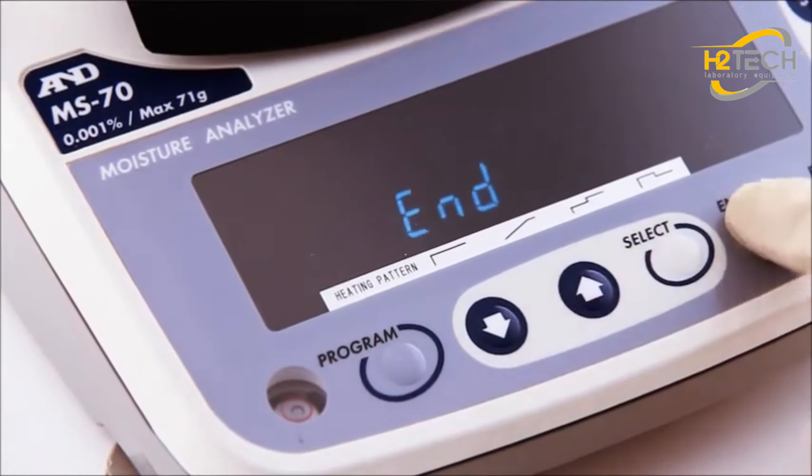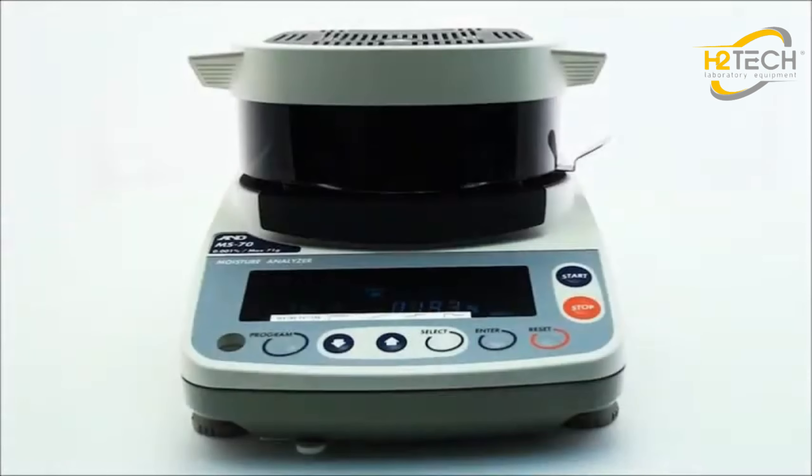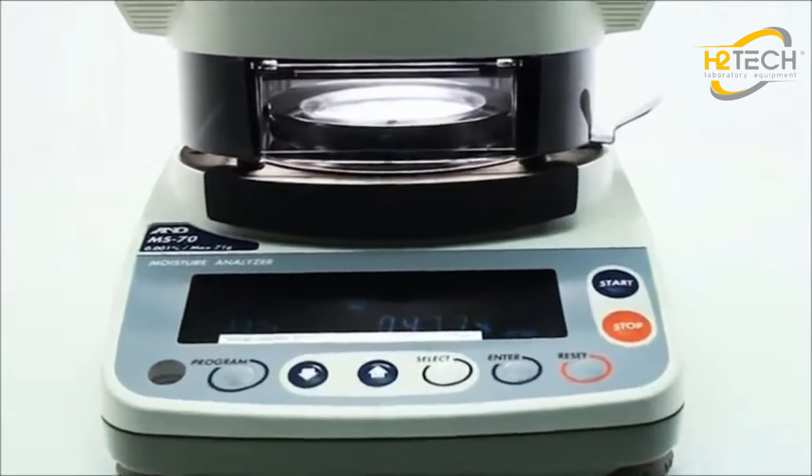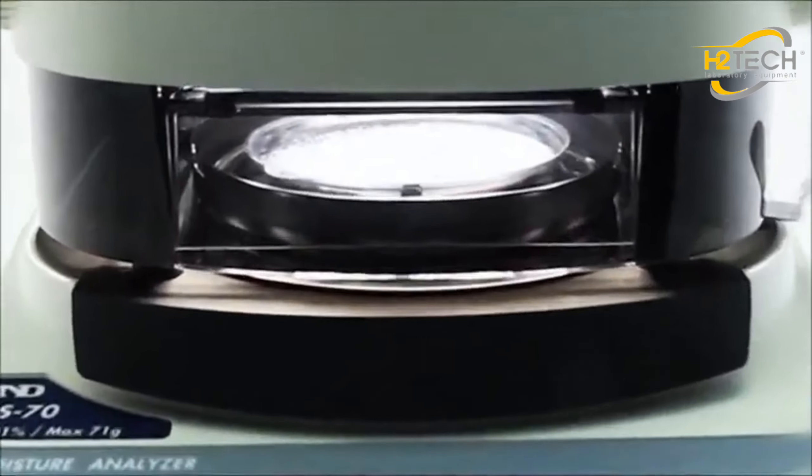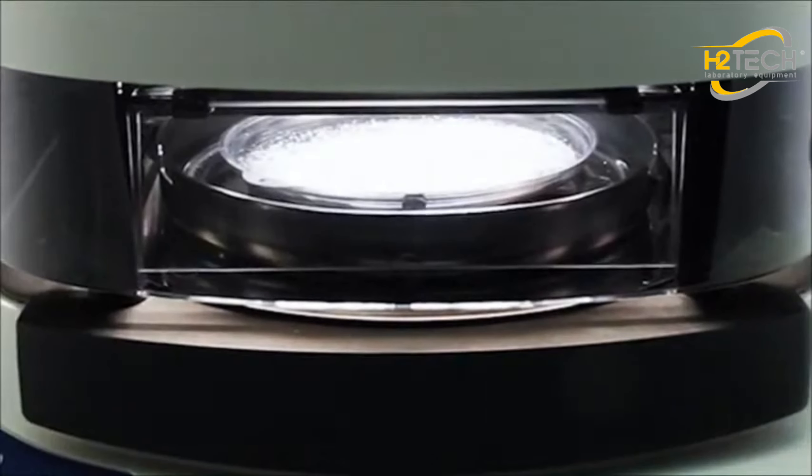A range of intelligent features helps assure accurate results. With the progress window, first offered by A&D, you can observe the drying process and be sure that the sample is not being burnt or scorched.